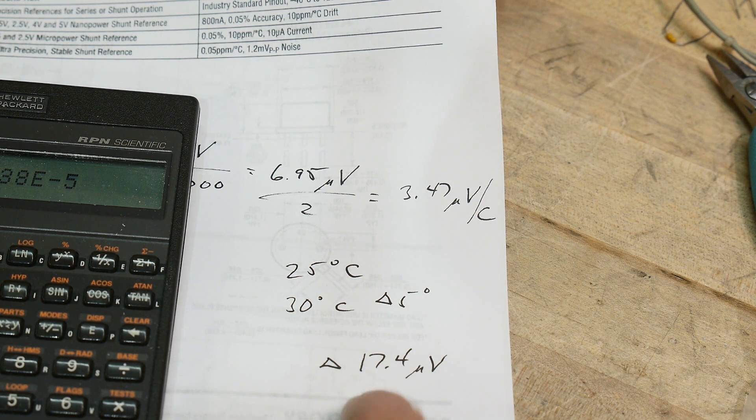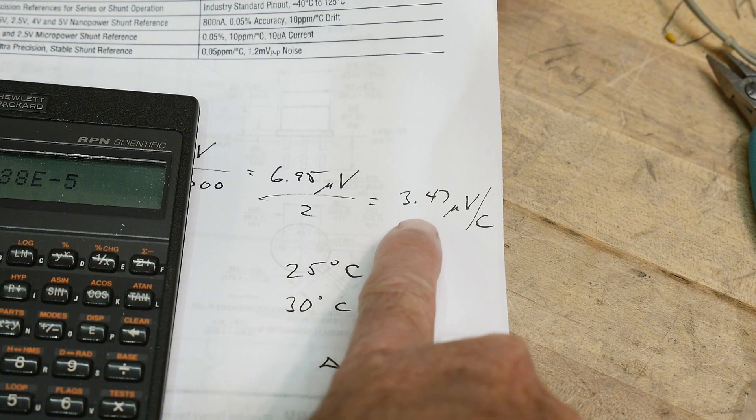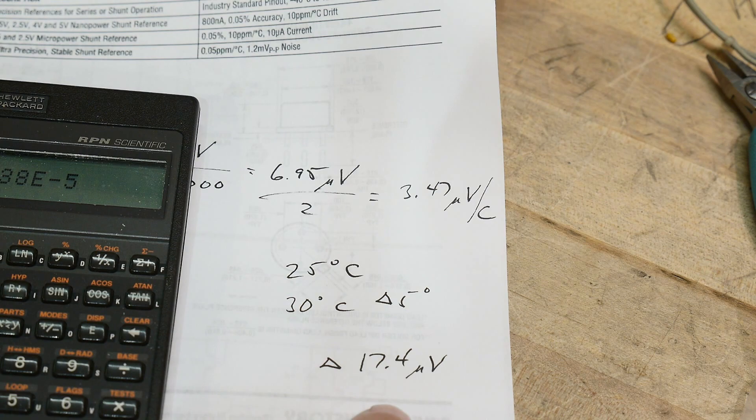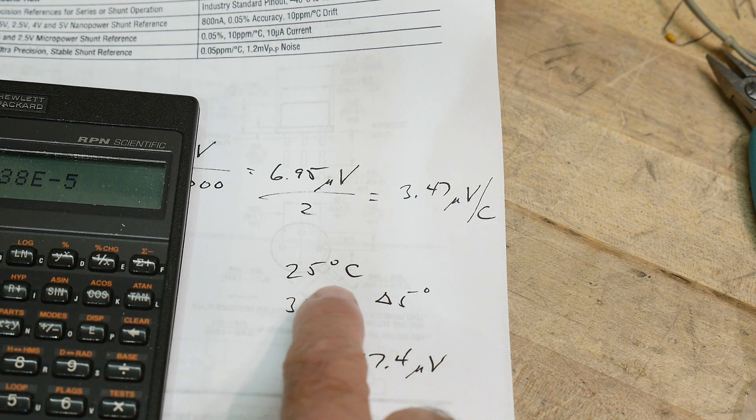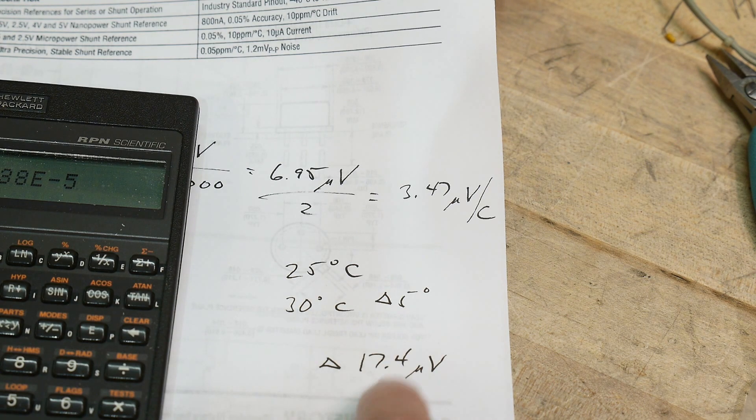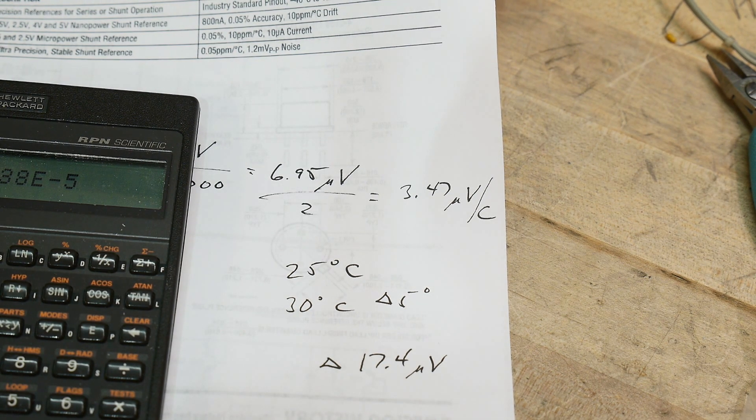You would take this number, multiply it by five, and you would get 17.4 microvolt delta. So five times 3.47 is 17. If you calibrated your instrument at 25°C but you used it at 30°C, you're going to have an error of 17 microvolts. That's pretty low.